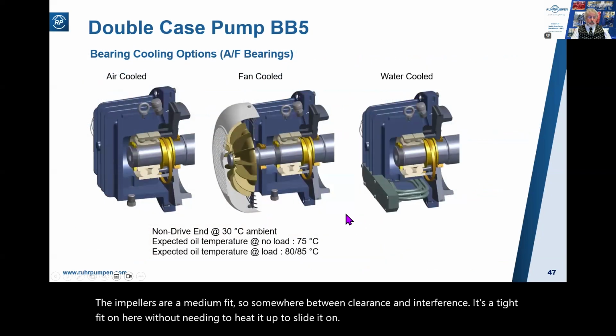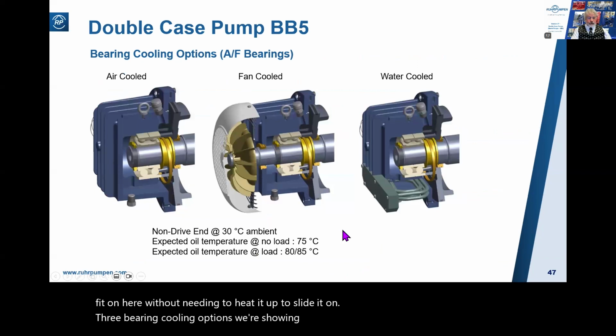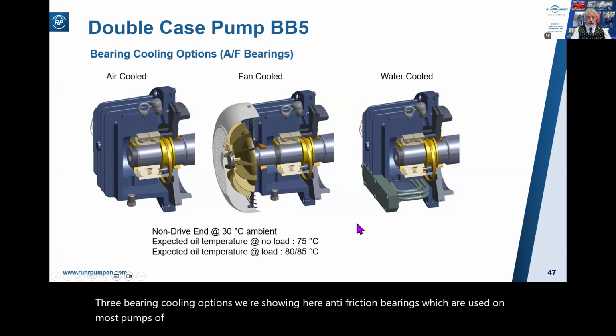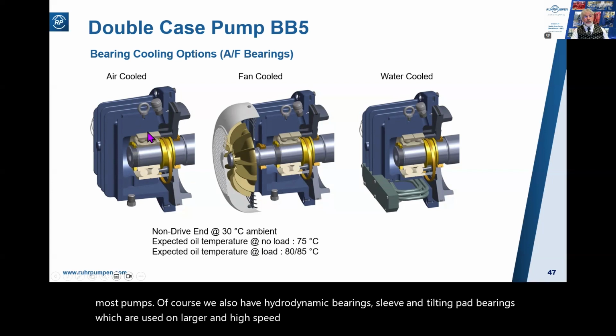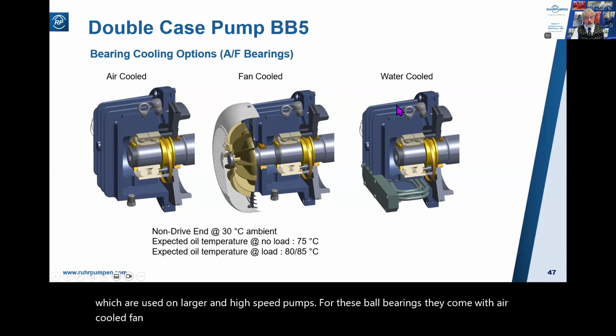Three bearing cooling options. We're showing here anti-friction bearings, which are used on most pumps. Of course, we also have hydrodynamic bearings, sleeve and tilting pad bearings, which are used on larger and high-speed pumps. For these ball bearings, they come with air-cooled, fan-cooled, or water-cooled, according to the temperature of your pumpage.